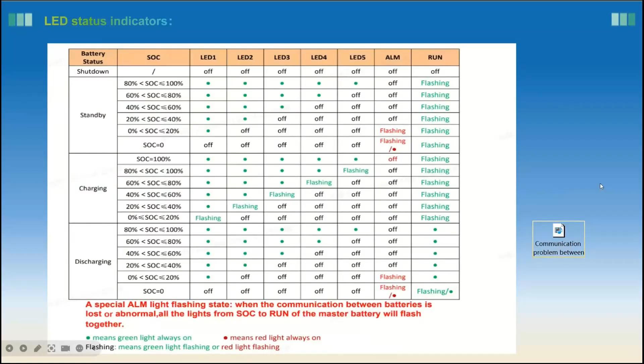Okay. And here are some common faults and a conclusion that can better help our installers or end users fix some easy problems. For example, the first is the indicator does not respond after we press the power button to turn on the battery. Maybe the total voltage is lower than 25 or the BMS was damaged. In this case, we first check whether the voltage is normal, and we can use a multimeter to measure the voltage and confirm. If the voltage is normal, we can replace the BMS to fix the problem.